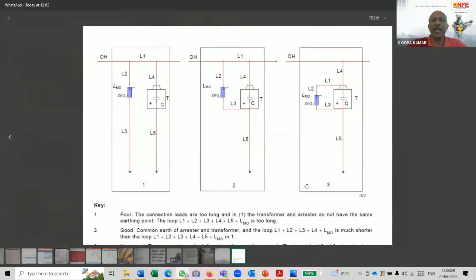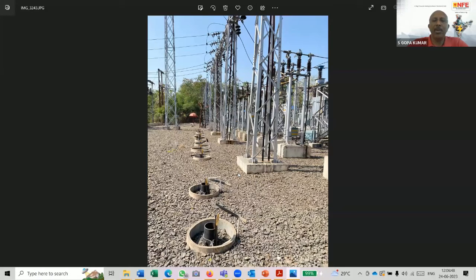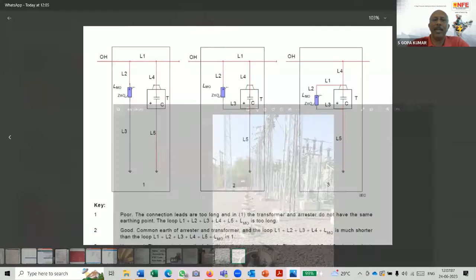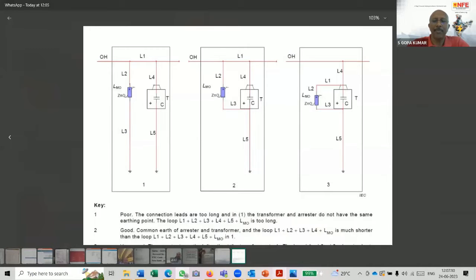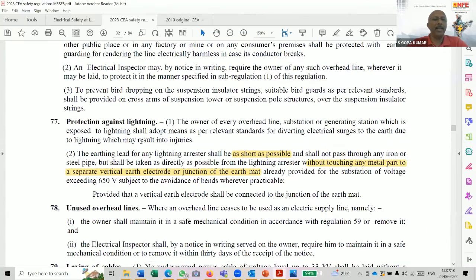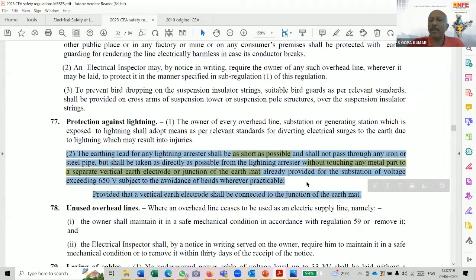That means the lead length of the surge arrestor has to be as short as possible. Now, if you look at the earlier picture which I showed, the lead length is quite large. Technically speaking, once you have a longer lead length, the surge arrestor is like a showpiece. It is never going to work, because in the lead length there will be more potential drop. As a result, the surge arrestor is not going to be effective, which is explained in the rules. Now, coming back to the regulation, I would say even if paragraphs number 2 and 3 were removed, the regulation would have been much better. What is your opinion on that, sir?